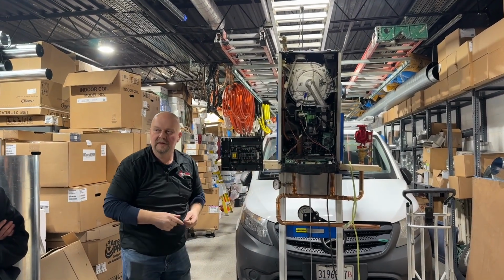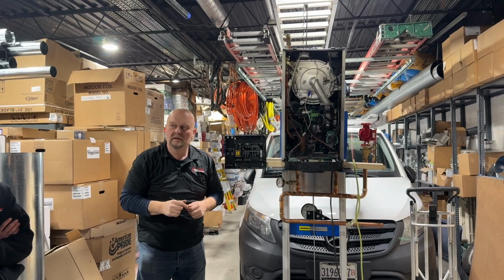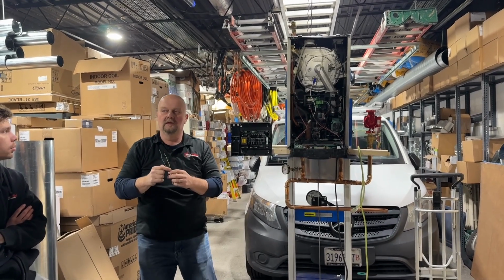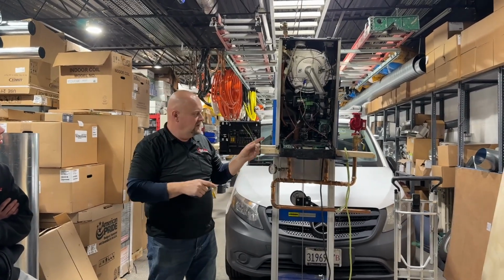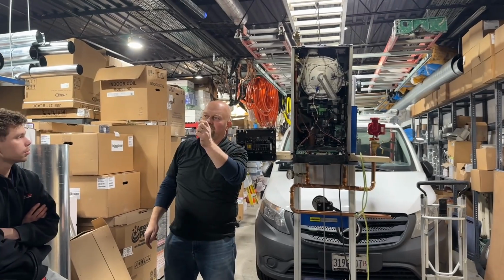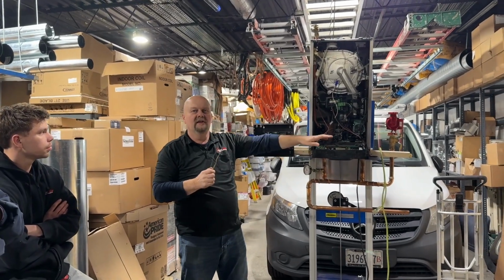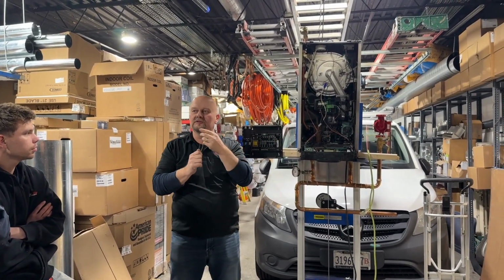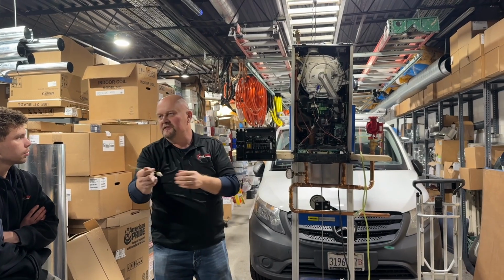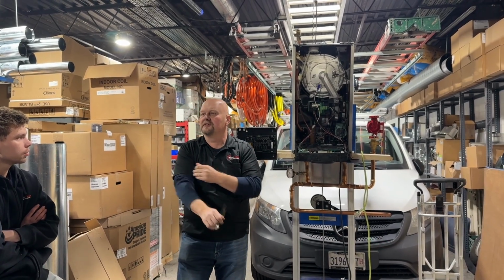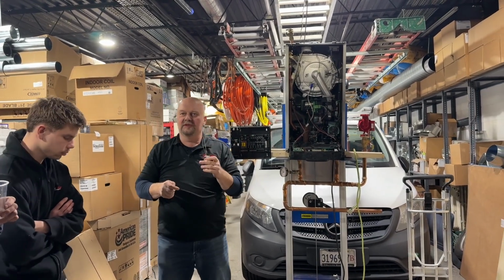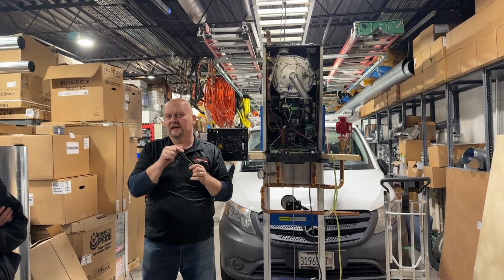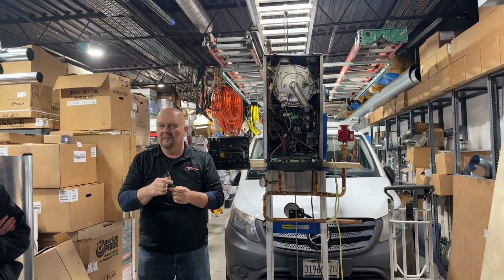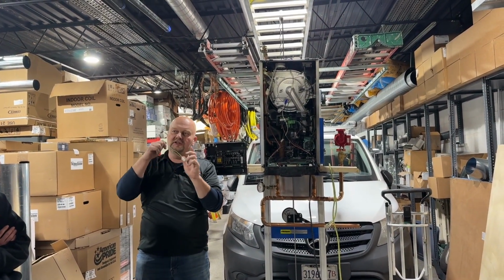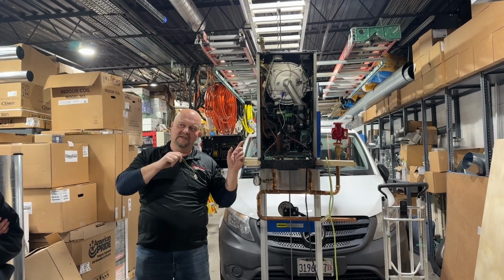Can't you apply 24 volts to the X and X? You cannot. This is a DC signal. So this needs to be closed, but any traditional thermostat with R and W, with its own battery, will close it. So just remember this is a DC signal, so this is not like your furnace per se. But remember, all you're doing is closing these two wires to fire this up.